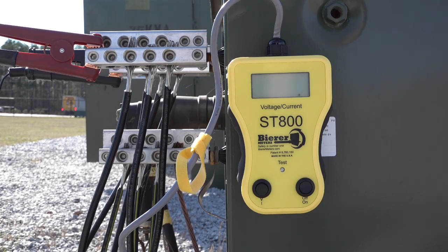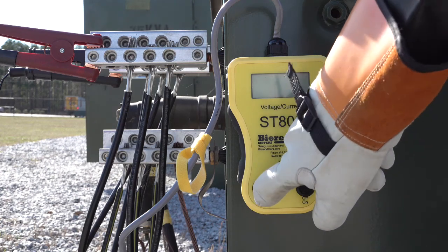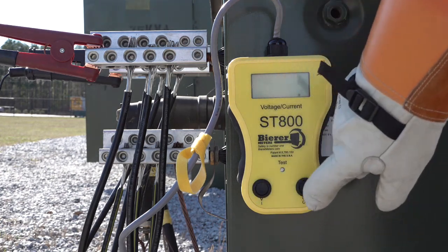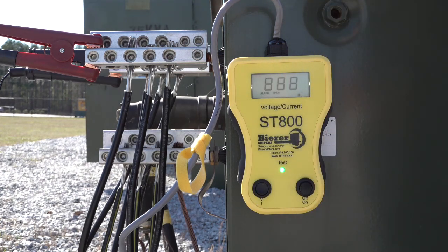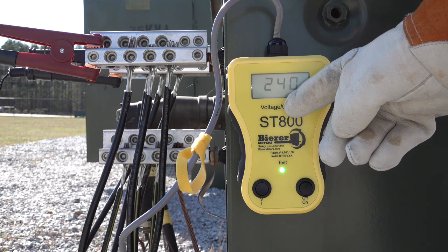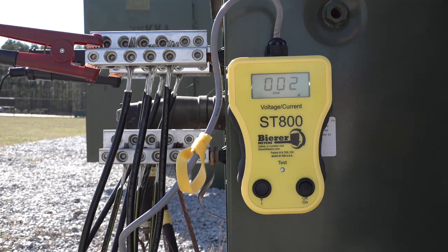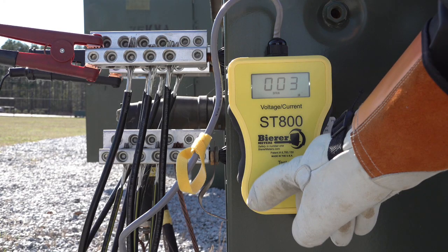Now we want to demonstrate how to use the ST800 to identify the primary source cable in a single-phase pad mount if the feed in and feed out are not labeled, or to verify labeling. While performing this test, always connect the red lead and the black lead to the hot bushings of the transformer. When performing this function of the ST800, it is important to remember which lead you have connected to the X1 bushing and the X3 bushing, as I'll show later in the video.